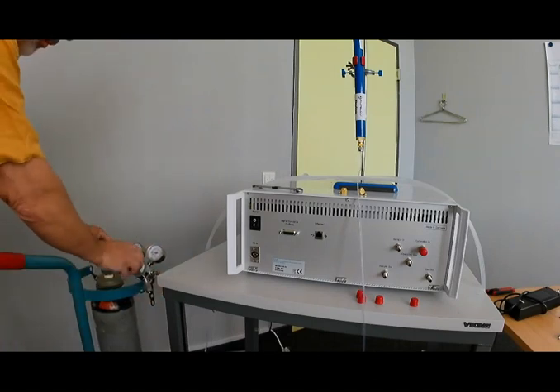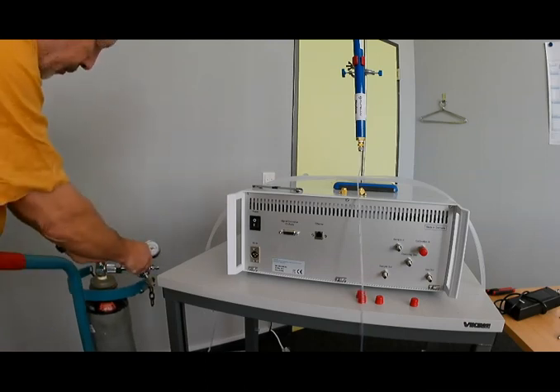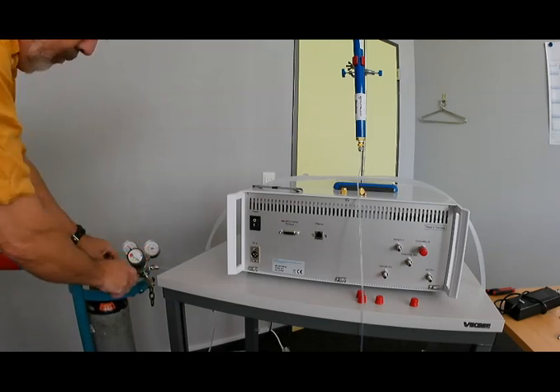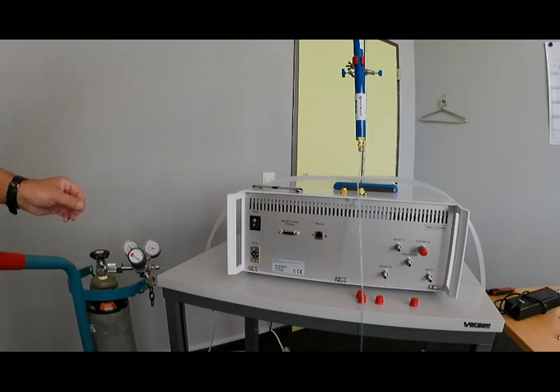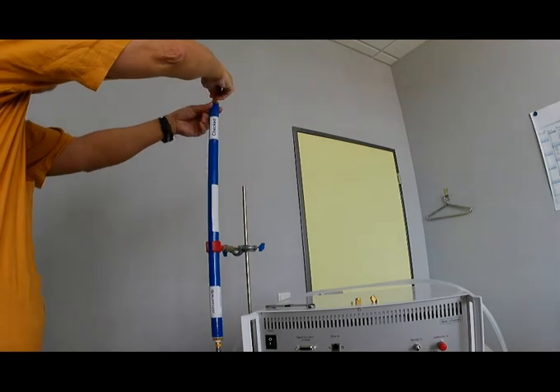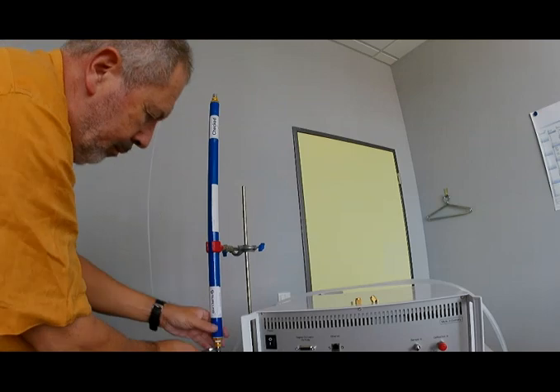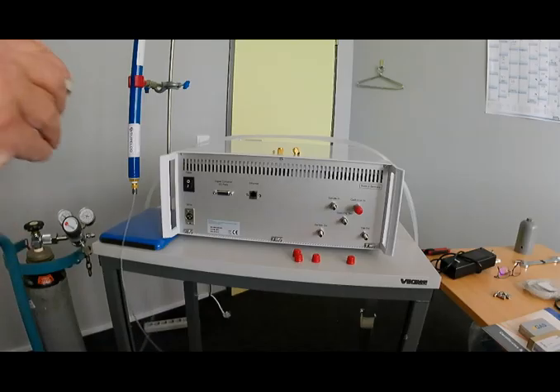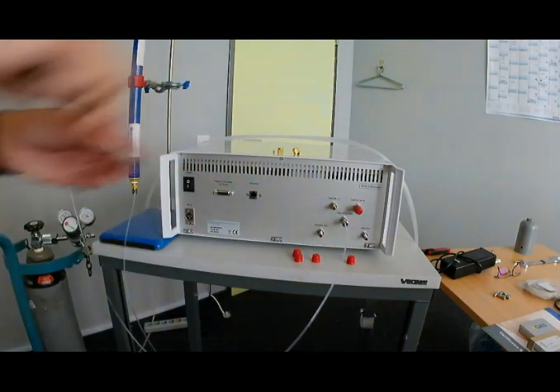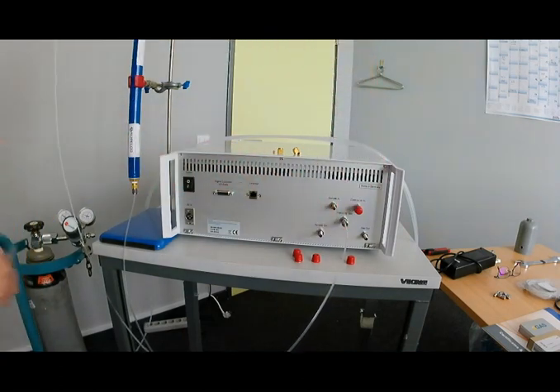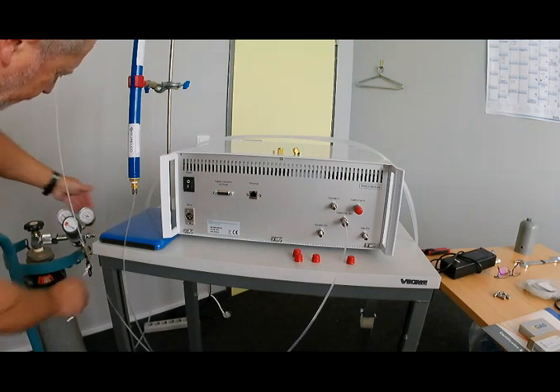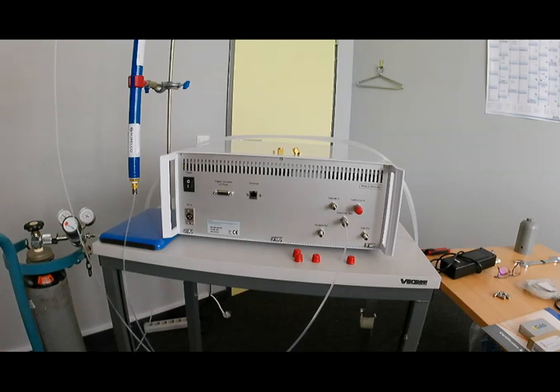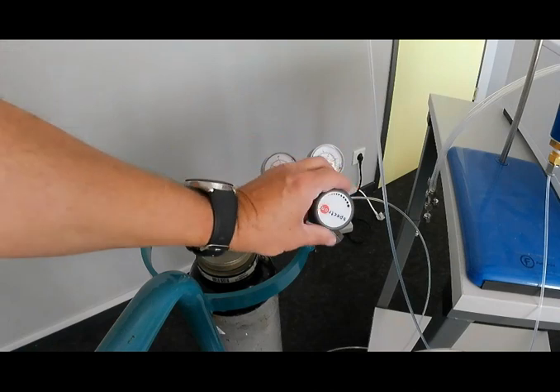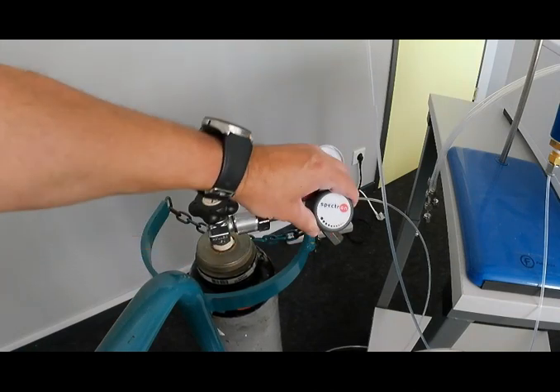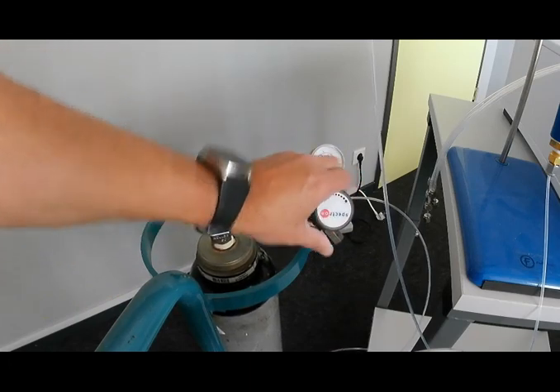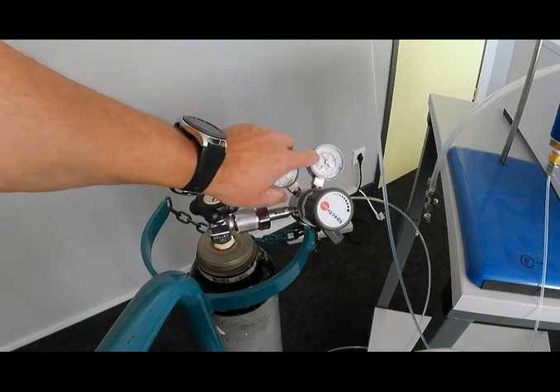We make sure that the pressure reducer is put to 0, and then we open the gas bottle and set the reducer to have a minimum flow through the molecular sieve. We now connect the outlet and verify that both connections are tight. The moisture trap outlet is connected to operating gas, the inlet, and we verify that the connection is tight, also the connection to the pressure reducer. We now are ready to set the pressure reducer to the right operating pressure conditions. It is recommended to have a value between 3 and 5 bar.